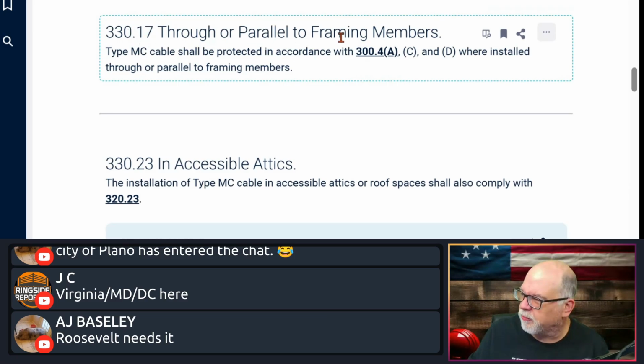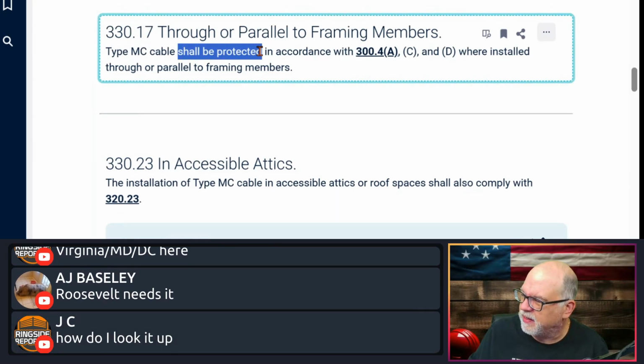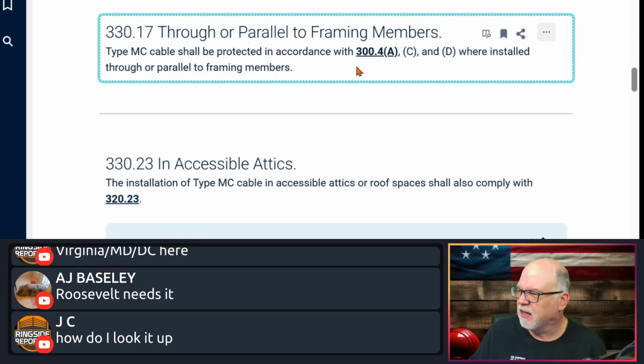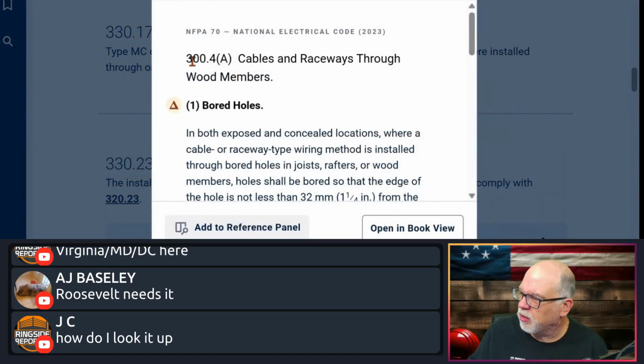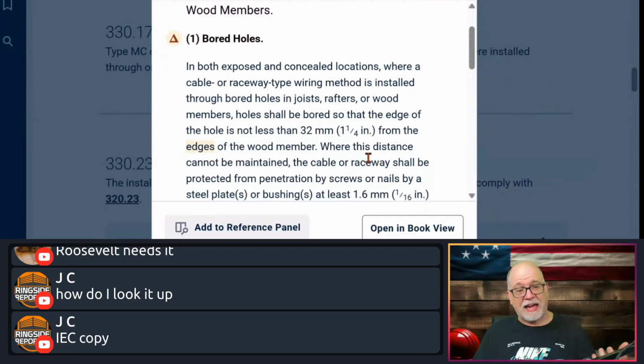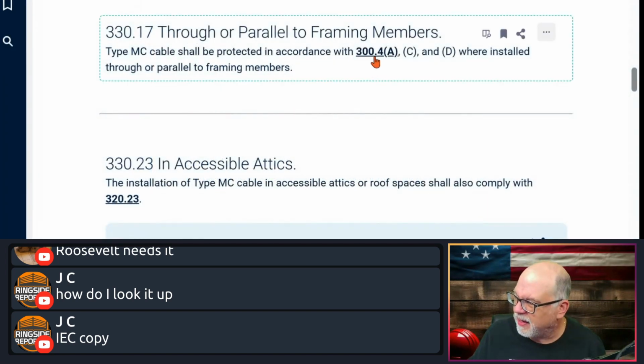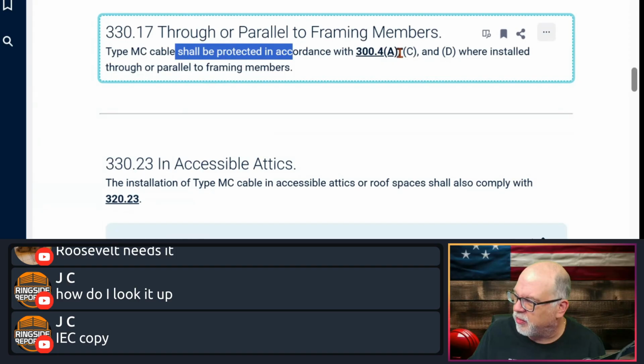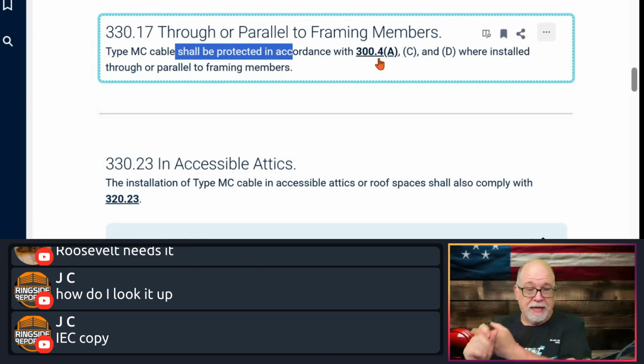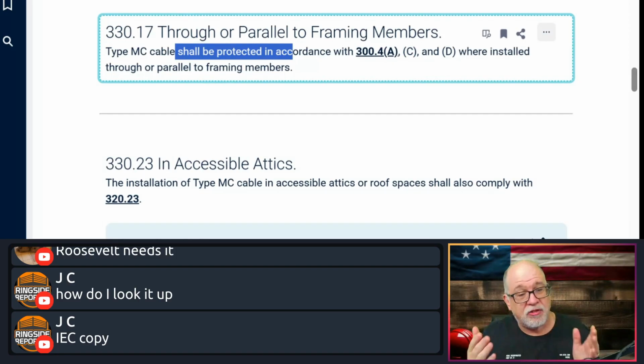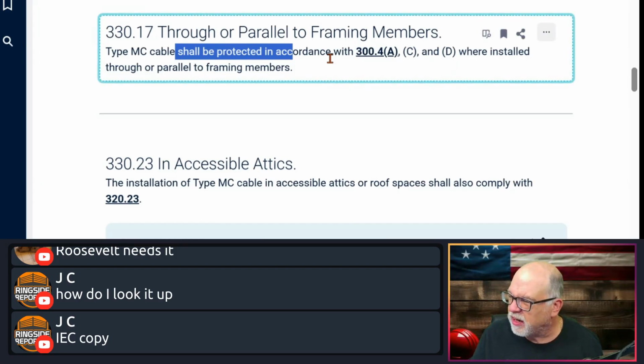330.17, through or parallel to framing members. MC cables shall be protected in accordance with 300.4(A), (C), and (D) where installed through or parallel to framing members. Okay. So I'll just show you 300.4(A). If you're going to take it through bored holes, then you're going to protect it exactly the same as you would non-metallic sheath cable. It says shall be protected in accordance, and then you got C and D. So read up. When you run it parallel, that means you're still going to maintain 1.25 inches, or you're going to have protective strips and things like that. So you still have the rules that you have to meet.